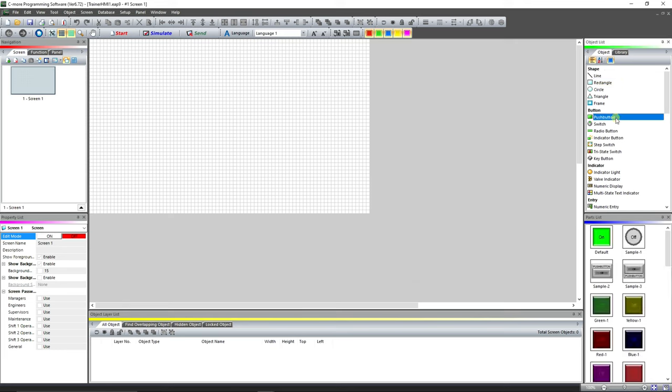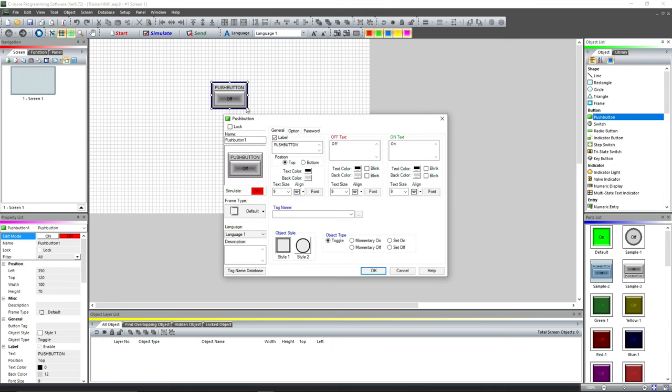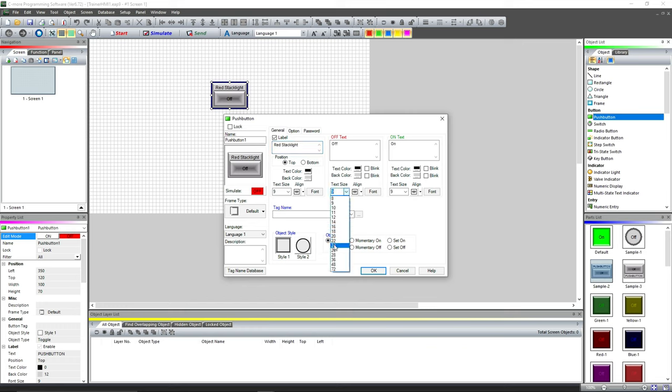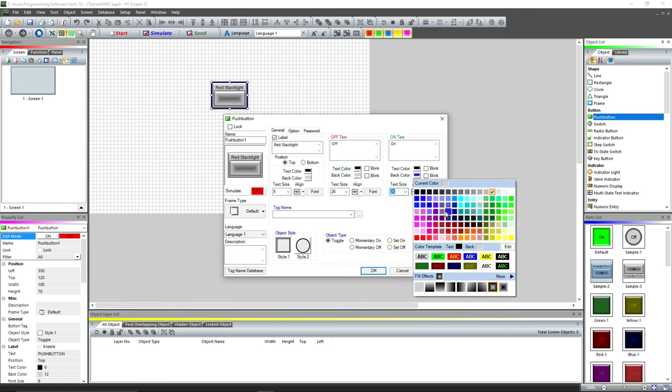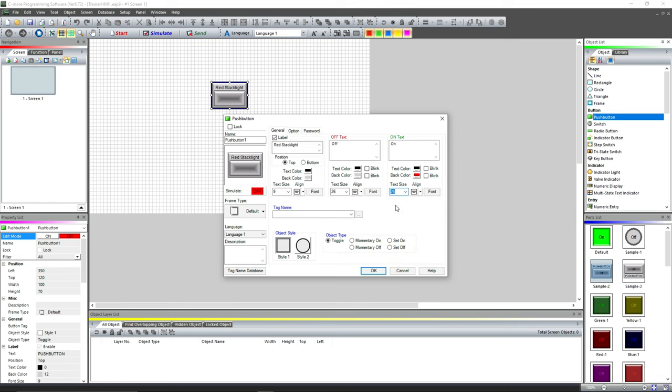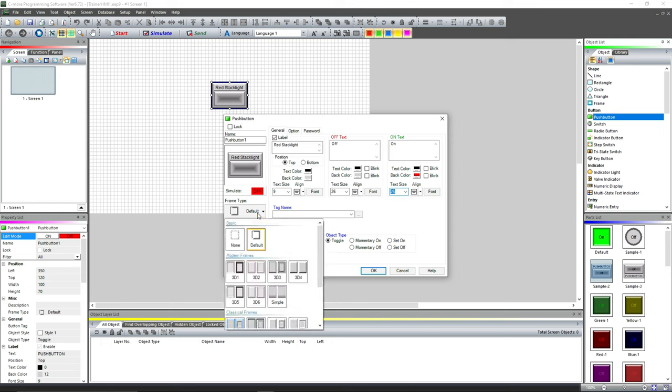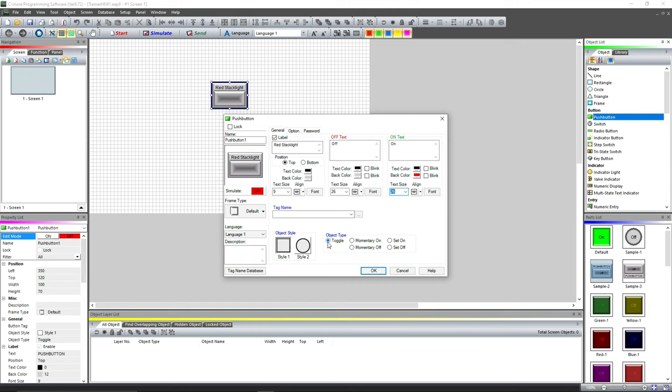We're going to do a push button with a frame right here. We're going to drag it up here and drop it. The first one we're going to call it Red Stack Light. We're going to make our font really big because we're going to try to take up some space on this screen just for this test. This is a red stack light, so when it's on I want the button to turn red. If you look around here a little bit, you've got a lot of options. You've got different frame styles, you've got whether you want this to be a toggle, which we're going to use it as a toggle here. Normally in an actual working program I wouldn't use the HMI to latch something on—I do that in the PLC and it would be a momentary button on the HMI. But just for simplification we're going to use it as a toggle on this.